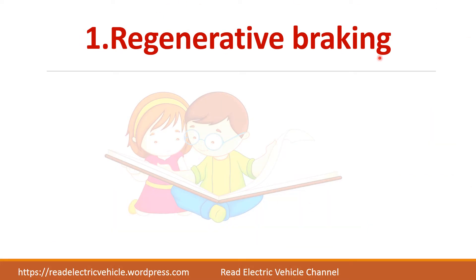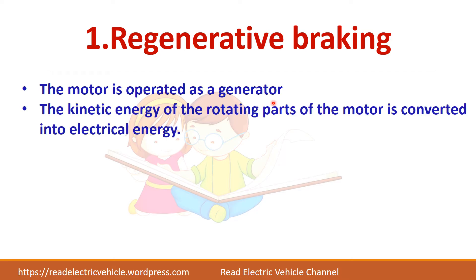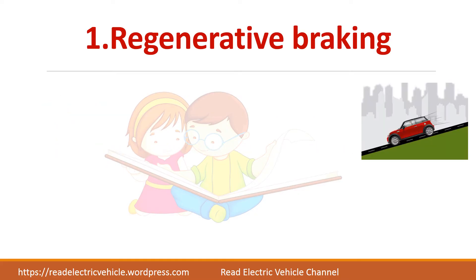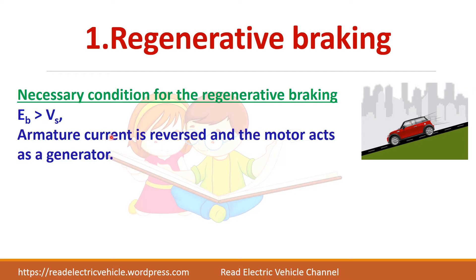In regenerative braking, the motor is operated as a generator and the kinetic energy is converted into electrical energy, which is returned to the supply source. The necessary condition for regenerative braking is that the supply should be able to receive the energy from the load. For that, the back EMF should be greater than the supply voltage Vs, so that the current will reverse, the motor will act as a generator, and give the supply back to the source.